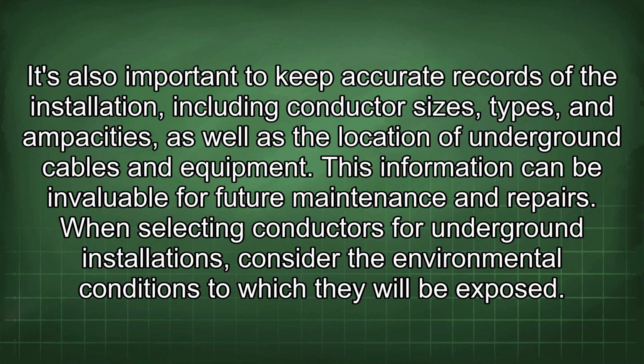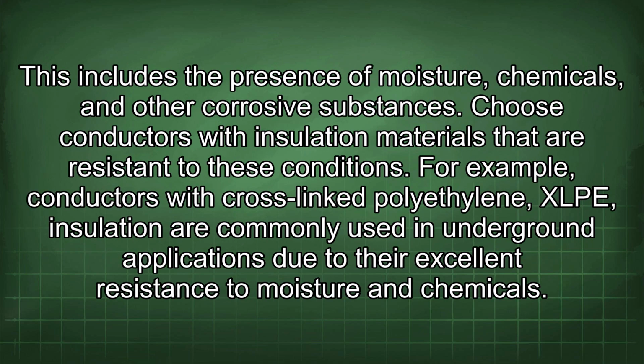When selecting conductors for underground installations, consider the environmental conditions to which they will be exposed. This includes the presence of moisture, chemicals, and other corrosive substances. Choose conductors with insulation materials that are resistant to these conditions. For example, conductors with cross-linked polyethylene XLPE insulation are commonly used in underground applications due to their excellent resistance to moisture and chemicals.